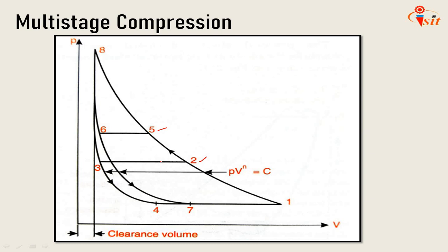It is seen that as the delivery pressure for a single stage reciprocating compressor is increased, so mass flow through the compressor decreases. Note that as the delivery pressure is increased, so also does the delivery temperature increase. Now if high temperature air is not a requirement of the compressed air delivered, then any increase in temperature represents an energy loss.